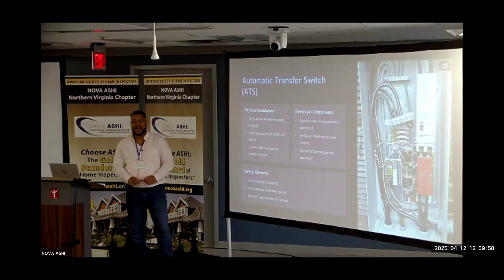Another thing, of course, is that the same applies to the ATS as to an electrical panel as far as clearance. Make sure that you have 30 inches of clearance in width and 36 inches in depth in front of the ATS as well.